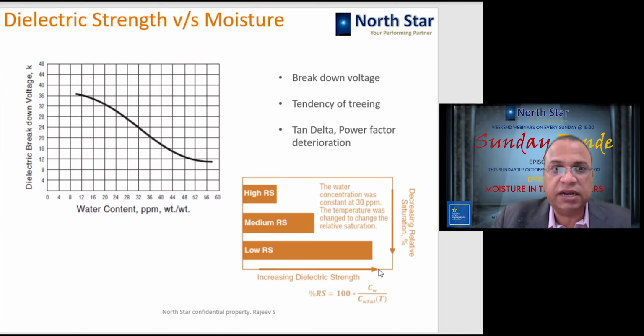The second parameter is the dielectric strength, which is affected because of moisture content. Here again a graph is there, which shows the dielectric breakdown voltage against the water content in ppm. Okay, so you can see here, as the moisture is high, the dielectric strength comes down. So what happens is that the BDV of the oil drops. Then treeing is a phenomenon in solid insulation, especially when the insulation is thick insulation blocks. The treeing happens because of moisture, and like partial discharges, treeing is also more or less a similar phenomenon, and that also happens at a lower voltage if moisture is there in the insulation. And then these important parameters also increase with the moisture.